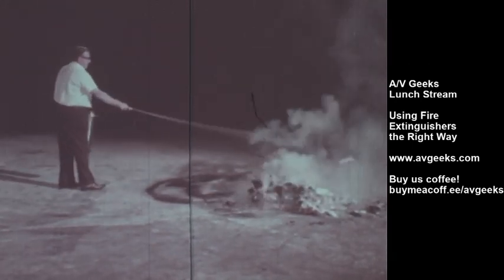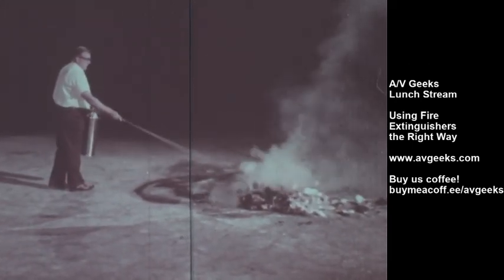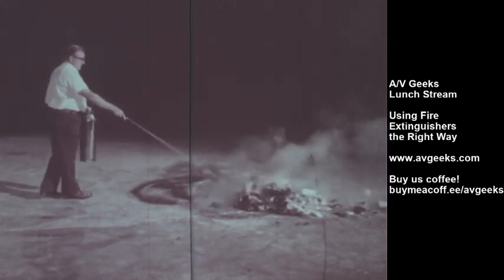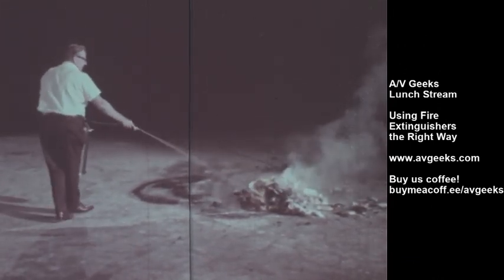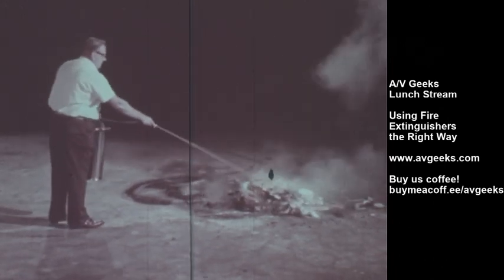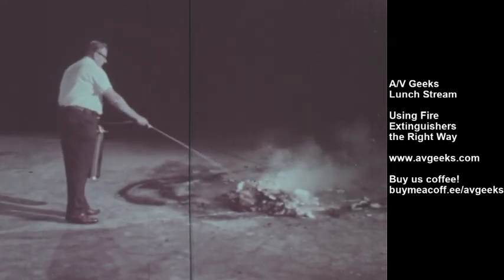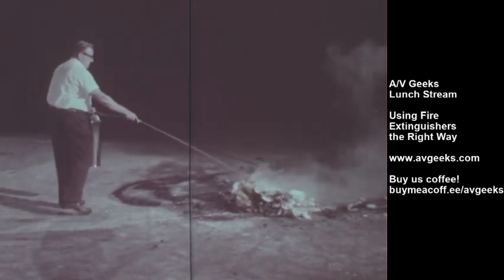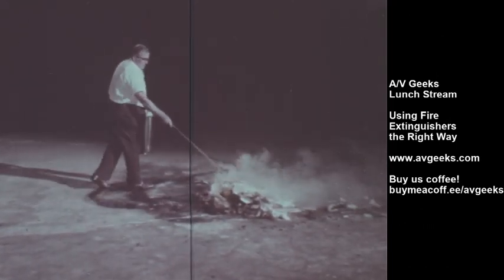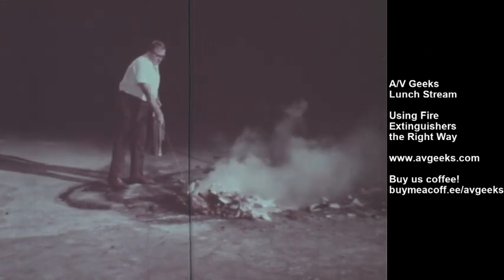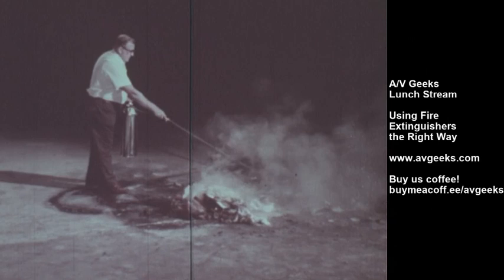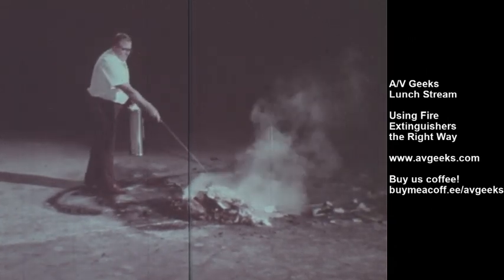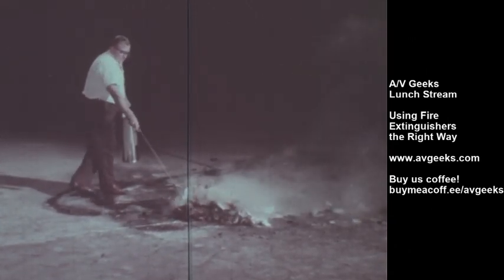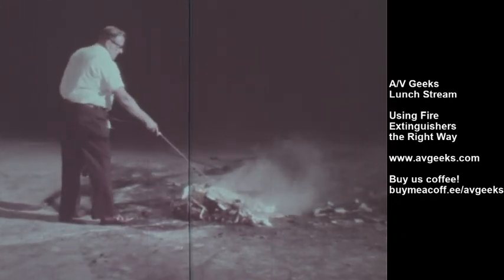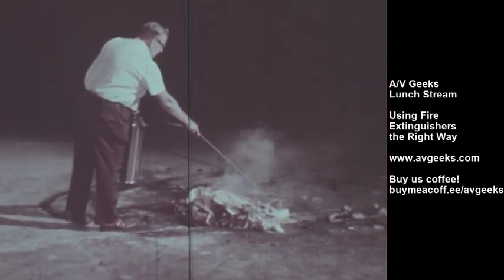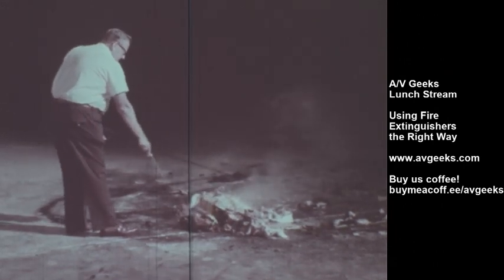The water puts out the fire by cooling the fuel, so it is important to soak the fire well, even after it appears to be out. Smoldering embers can cause the fire to flare up again. The water in this 2.5-gallon tank will last for about 60 seconds, although the stream can be stopped and started again. The maximum distance the stream will carry is about 40 feet. As with all extinguishers, the water extinguisher should be recharged immediately after use, no matter how much water may be left in the tank.